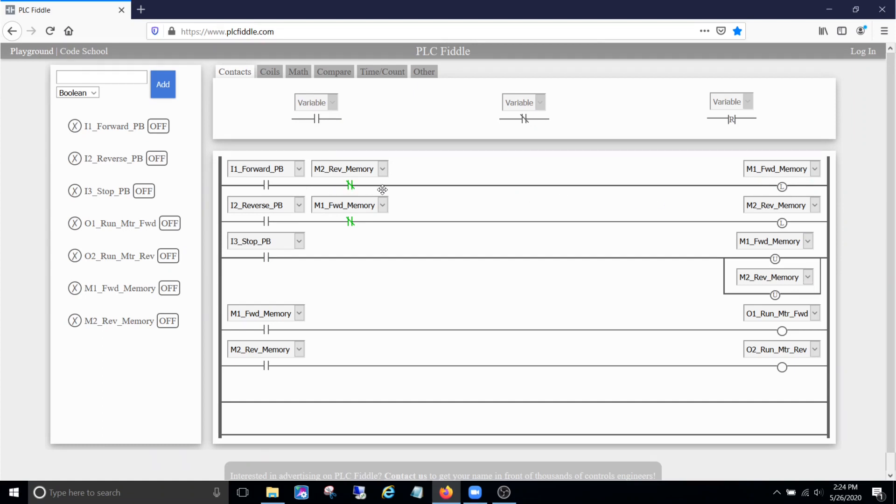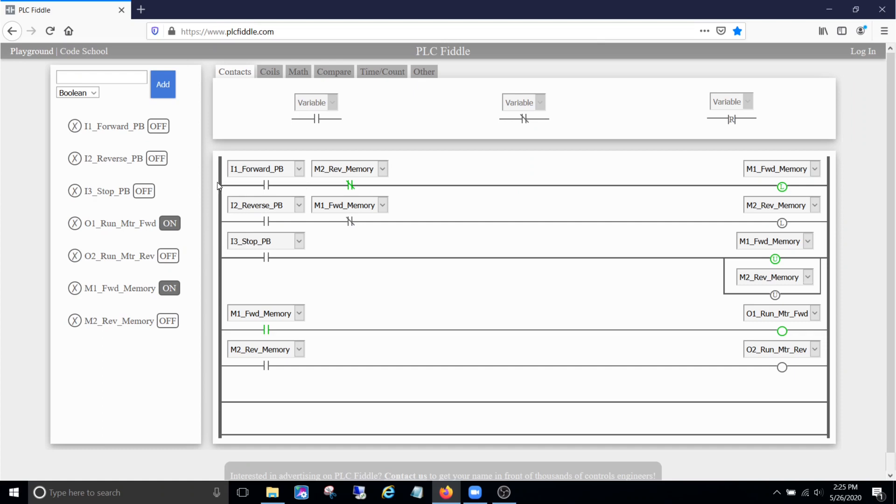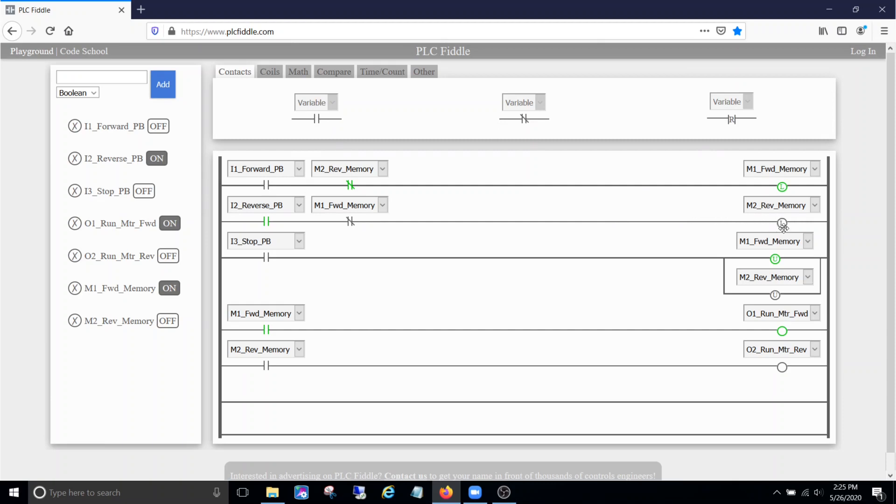So let's hit forward first. See, the reverse memory is off, so when we press this button, the logic can flow right through it and it's going to cut our forward memory on. See how it's latched there? I can let off the button. Now notice our latch M1 forward memory is on, so this M1 forward memory normally closed contact is false now. So when I hit this reverse push button, even though the button's on, this normally closed contact from that forward memory there is blocking the logic flow. So reverse cannot happen now.